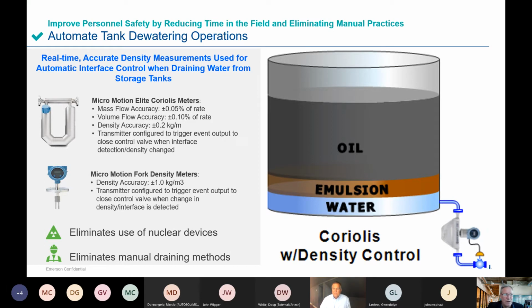What's important is that for a crude tank, they can install a Coriolis with density control and not pump that to the sewer. Pump it back up into the oil, because they're adding water at the desalter anyway. The only reason a crude tank has a water draw is because all the other tanks traditionally had one. Every crude tank shouldn't have a water draw that goes to the sewer, because it has a magnificent amount of benzene emissions that are horrible for worker exposure and the environment.